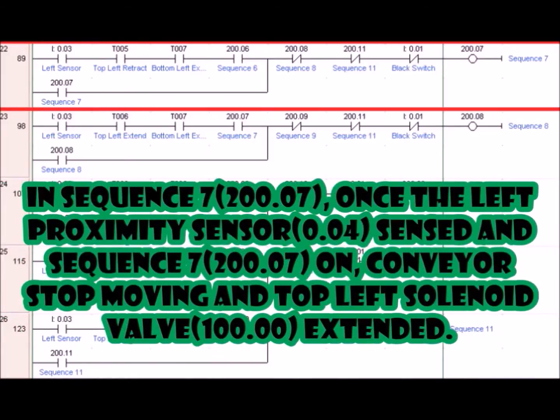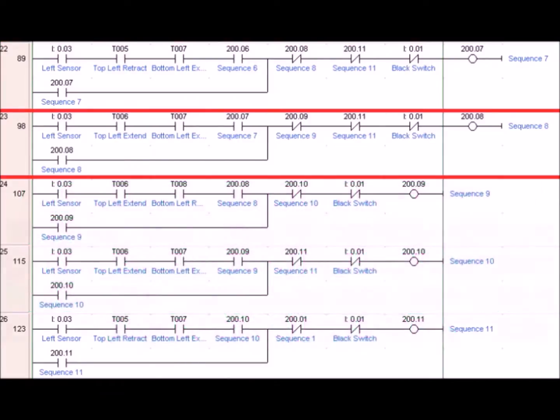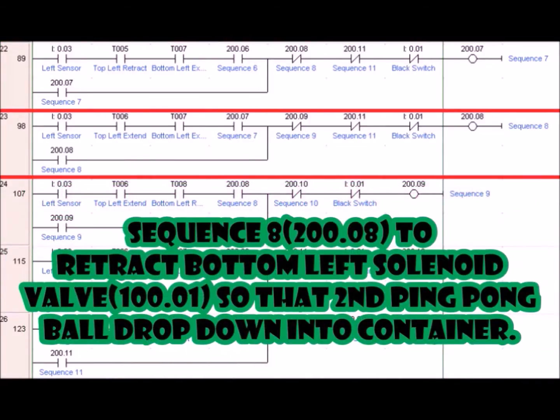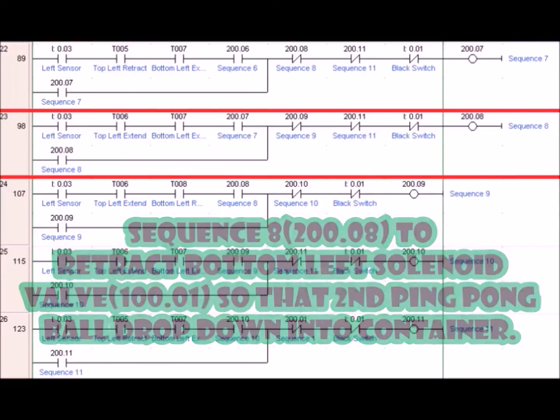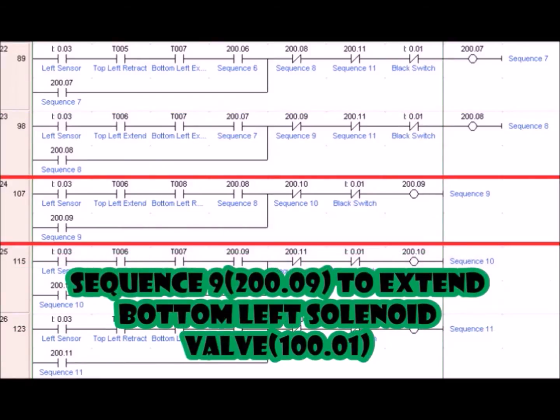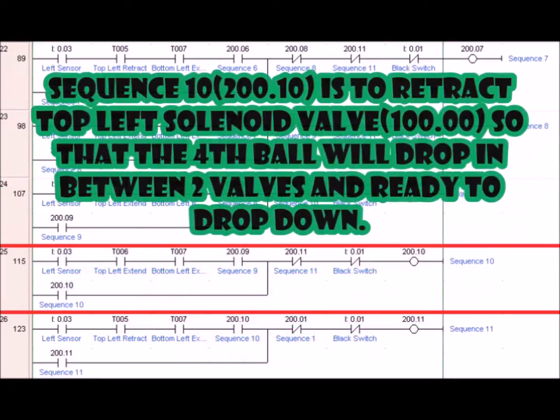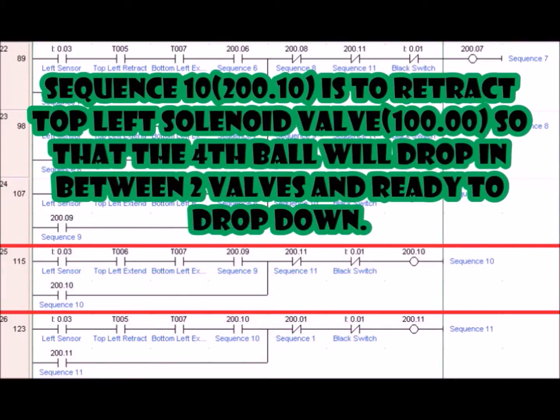In sequence 7, once the left proximity sensor senses and sequence 7 is on, the conveyor stops moving and the top left solenoid valve extends. Sequence 8 is to retract the bottom left solenoid valve so that the second ping pong ball drops down into the container. Sequence 9 is to extend the bottom left solenoid valve. Sequence 10 is to retract the top left solenoid valve so that the fourth ball will drop in between the two valves and be ready to drop down.